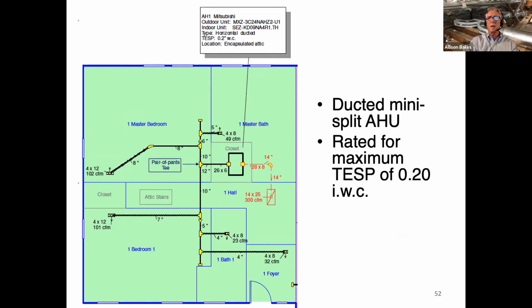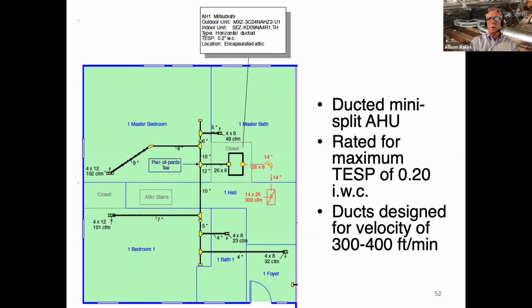But this is a ducted mini split rated for 0.2 inch of water column. And we usually design for lower velocities. The ACCA Manual D protocol says design for up to 900 feet per minute. If you design for lower velocity, the pressure drops are lower, and that helps your duct system. It means bigger ducts, though, to design for lower velocity.